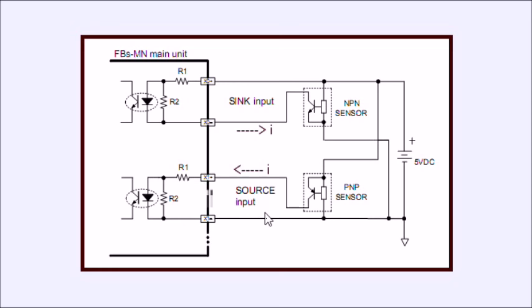Here's another illustration of how the two sensors are different. You can have an NPN transistor based sensor or a PNP transistor based sensor. And the NPN transistor based sensors will use a sinking input. That is the positive will go to the PLC, and then it's switched on to ground through the sensor. Or in the source input the positive side of the supply is connected to the sensor. The sensor switches on. It sources the current through the PLC and back to ground. That's their difference in source and sink, and this is important to understand based on the type of sensors you're using. Now if it's just plain mechanical switches, it doesn't matter if you use source or sink. But if you're dealing with solid state sensors such as hall devices, yes, you do have to worry about these issues.